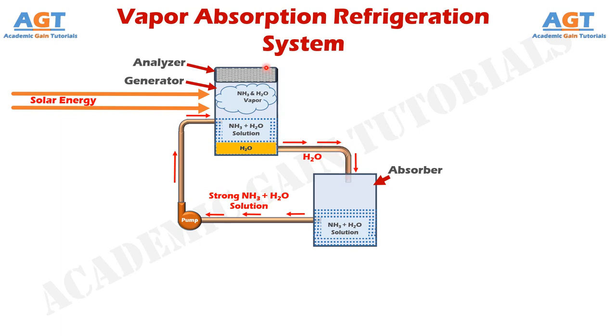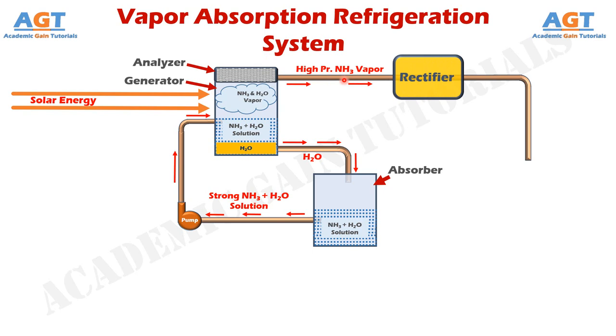Now, even after passing through the analyzer, there will be some proportion of water vapor mixed with this ammonia vapor. So, here we have a rectifier. This rectifier can also be called a separator, because it separates the remaining limited amount of water vapor present inside this ammonia vapor through the exchange of heat. Through the exchange of heat, this rectifier will convert the water vapor into liquid form and separate it from ammonia vapor. Then, this separated liquid water is passed back to the generator, from where it will ultimately reach the absorber.